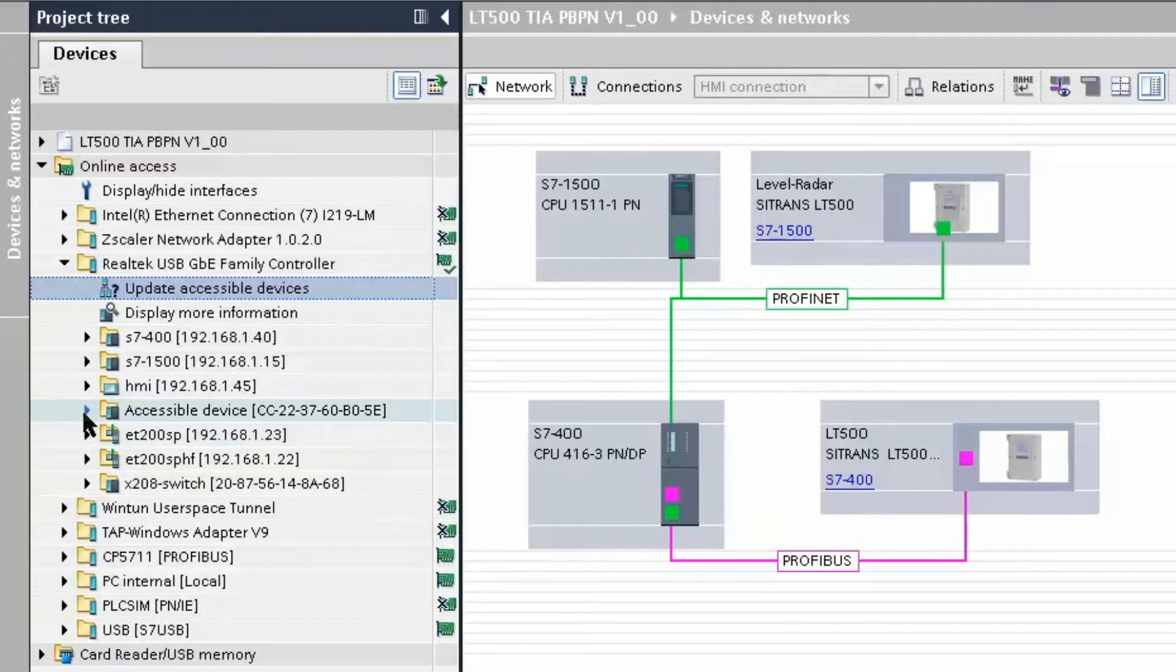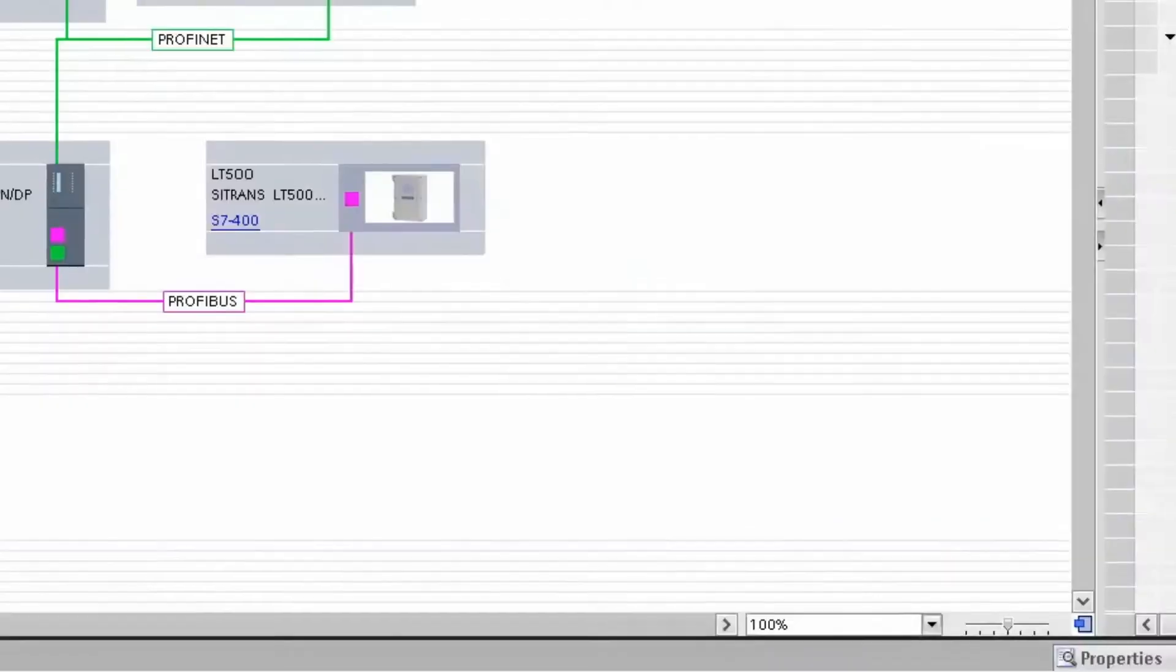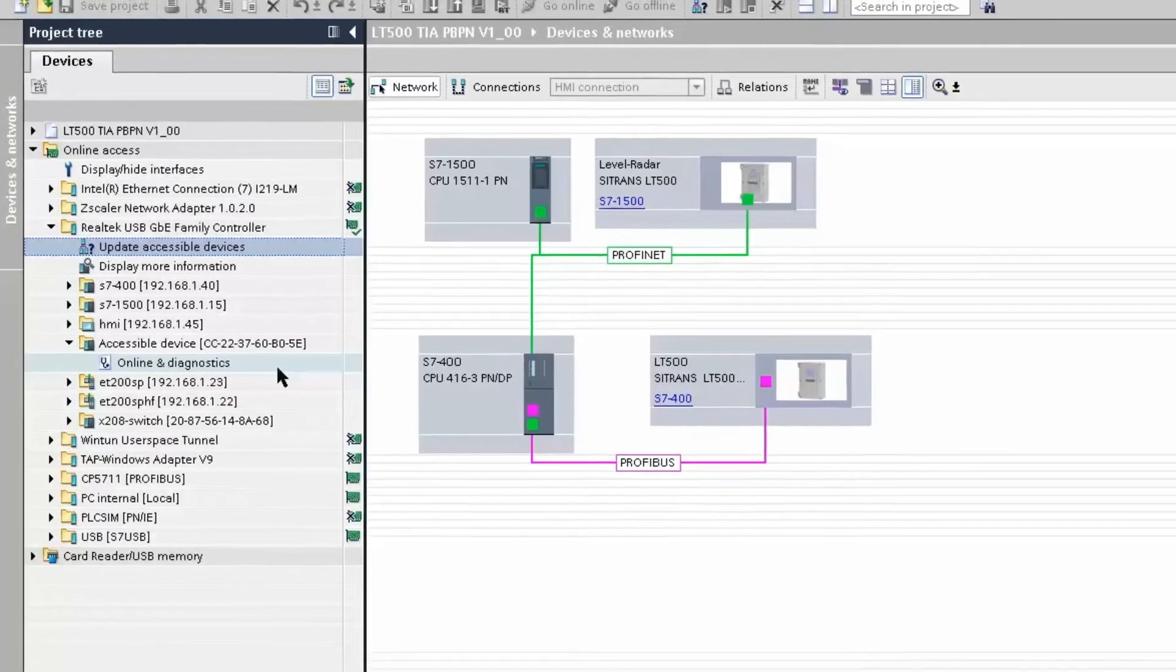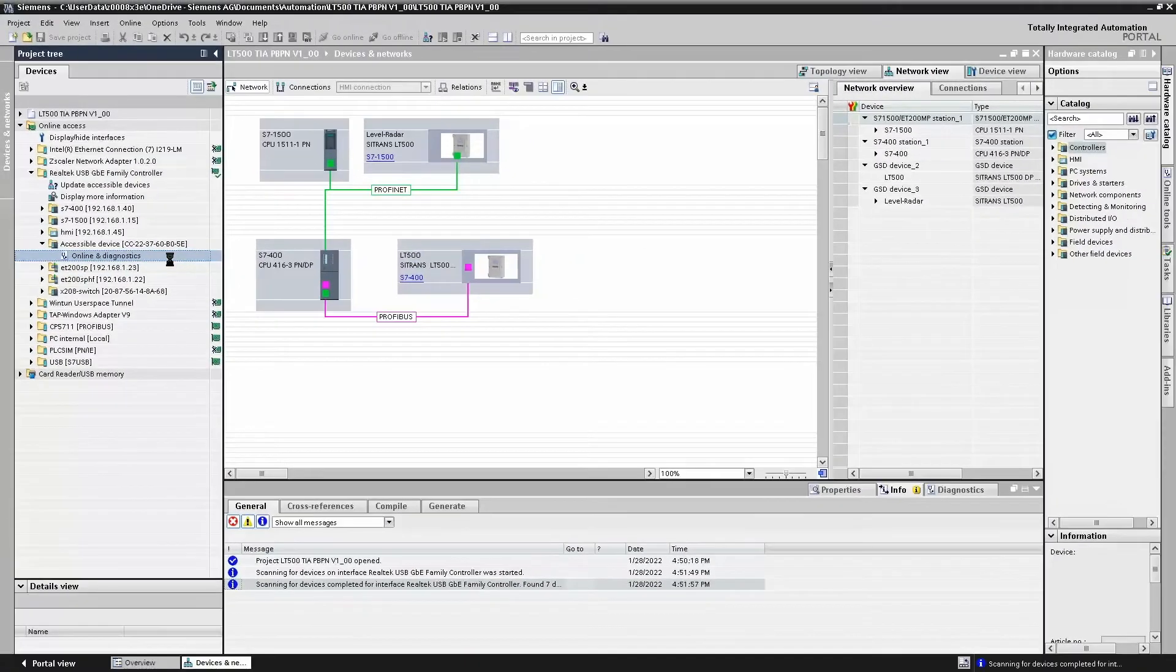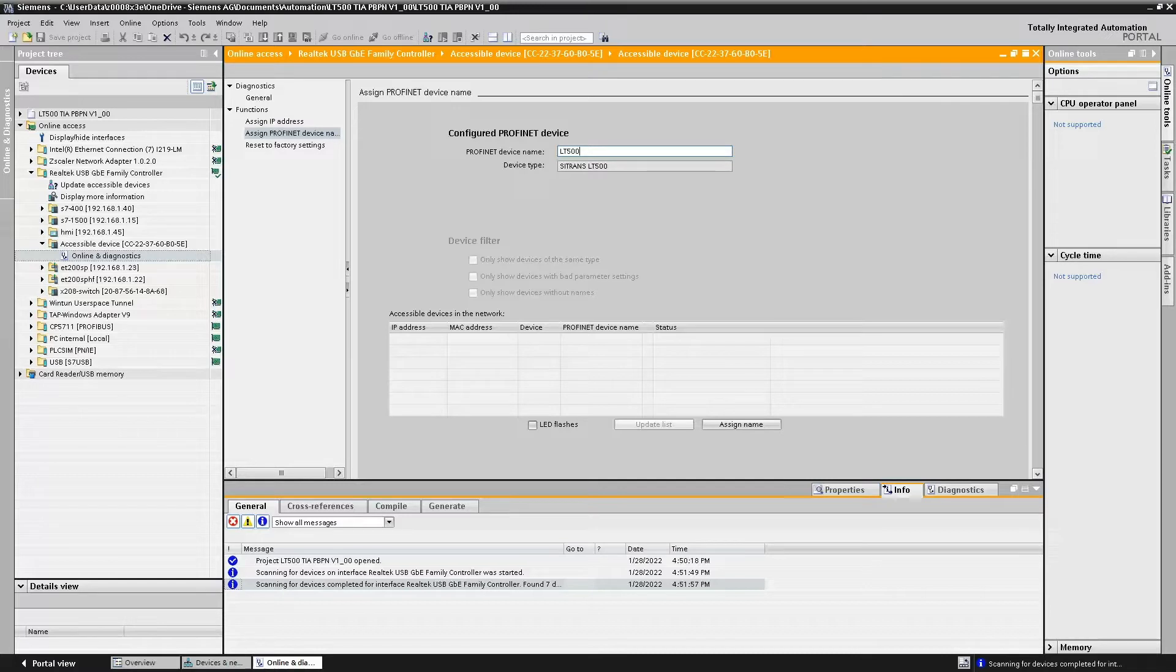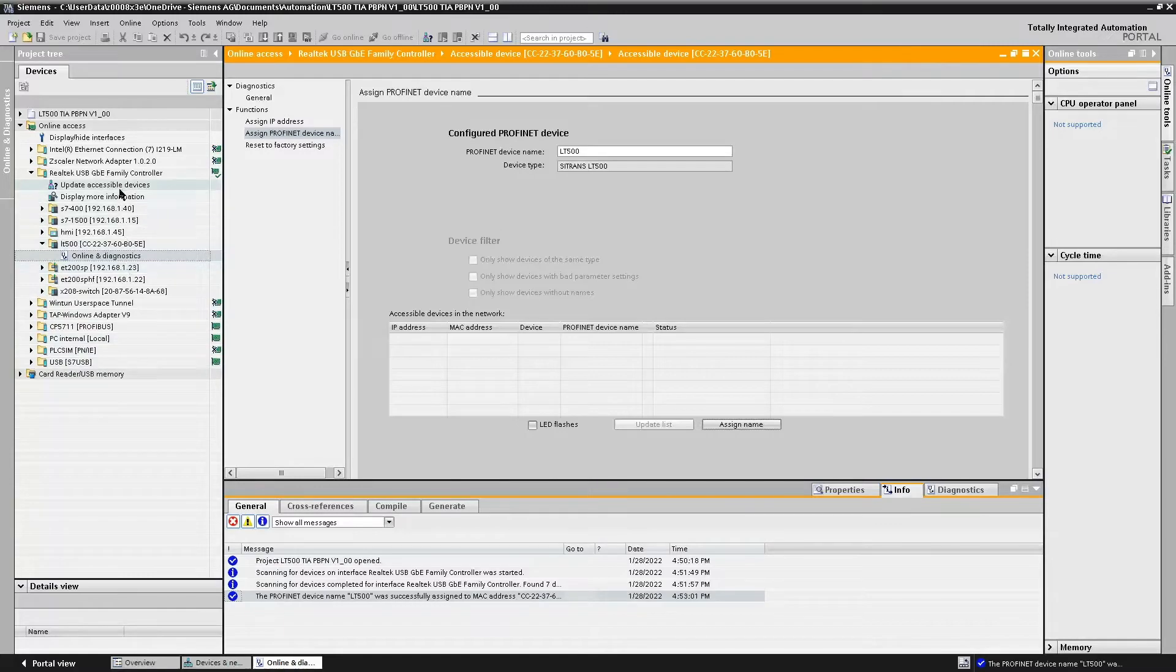So, if we look at our LT500 and we go to Online Diagnostics, this will allow us to go and assign a device name. In our example, let's use LT500 for the device name. We simply enter the device name, we hit the Assign button and now the name will be sent to the Sitrans LT500.